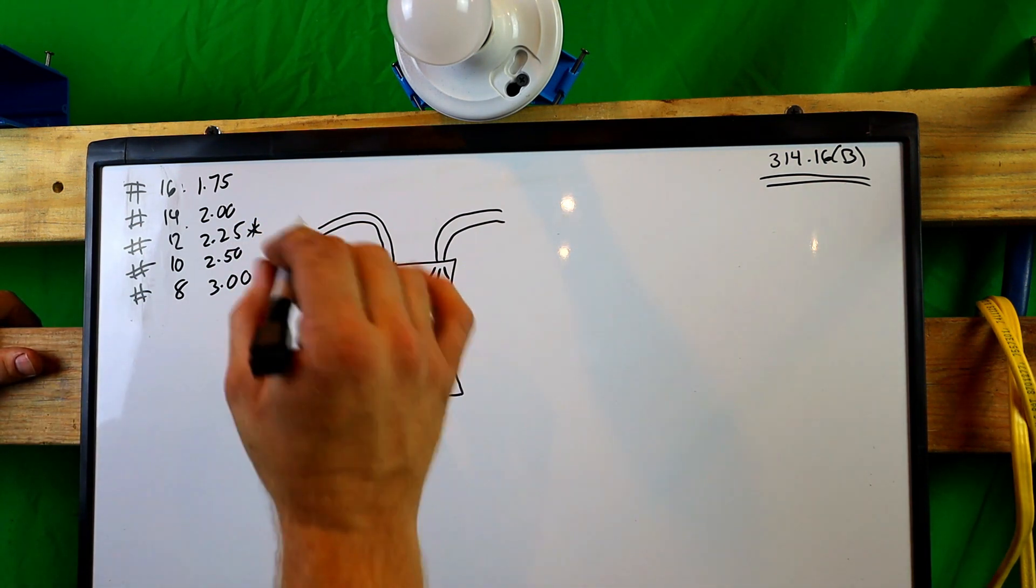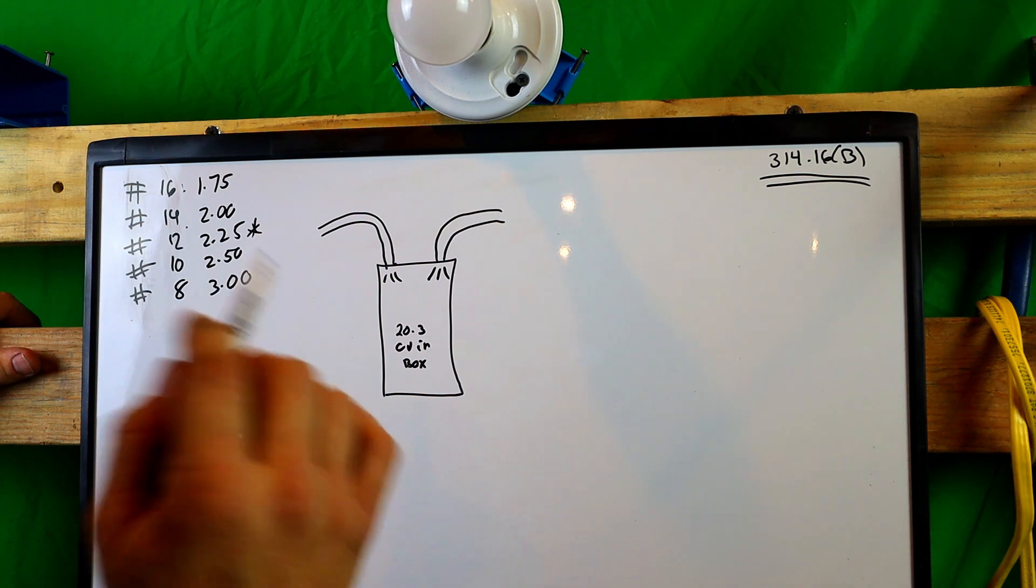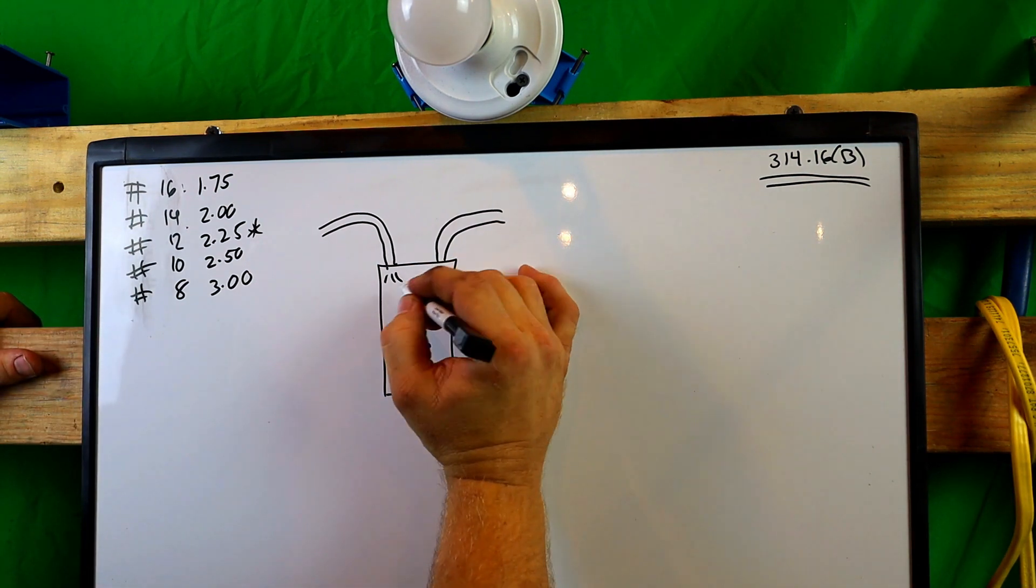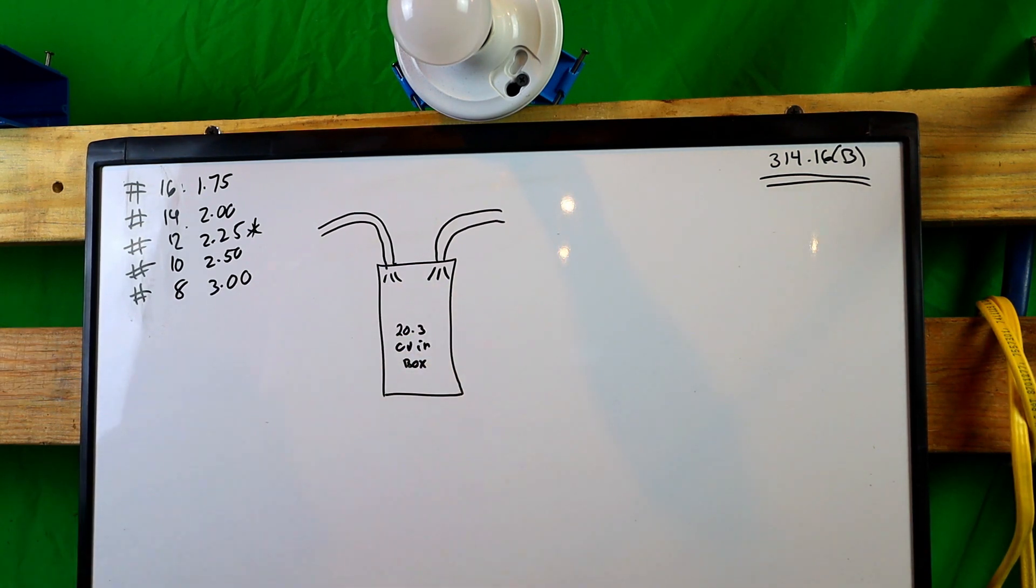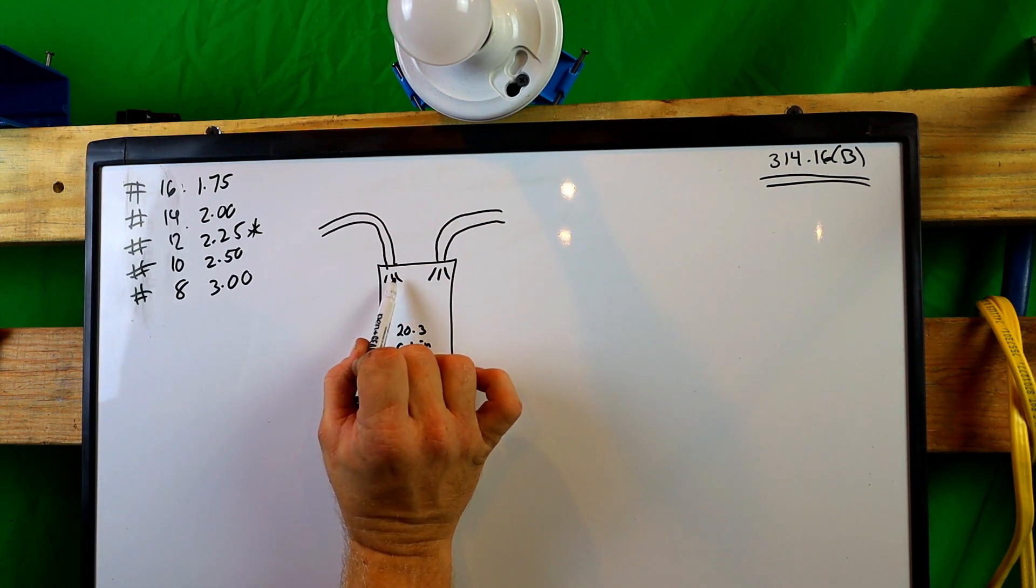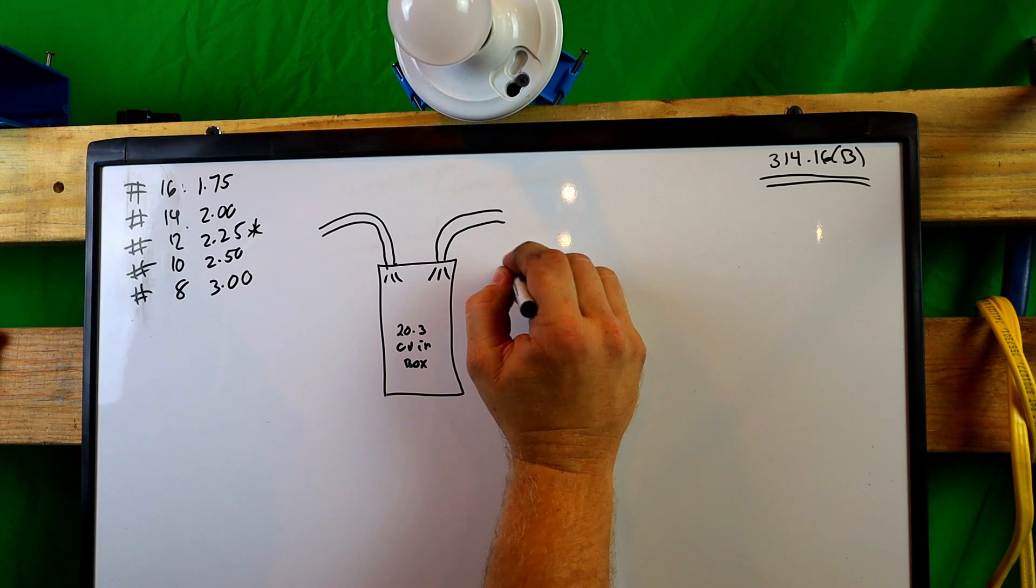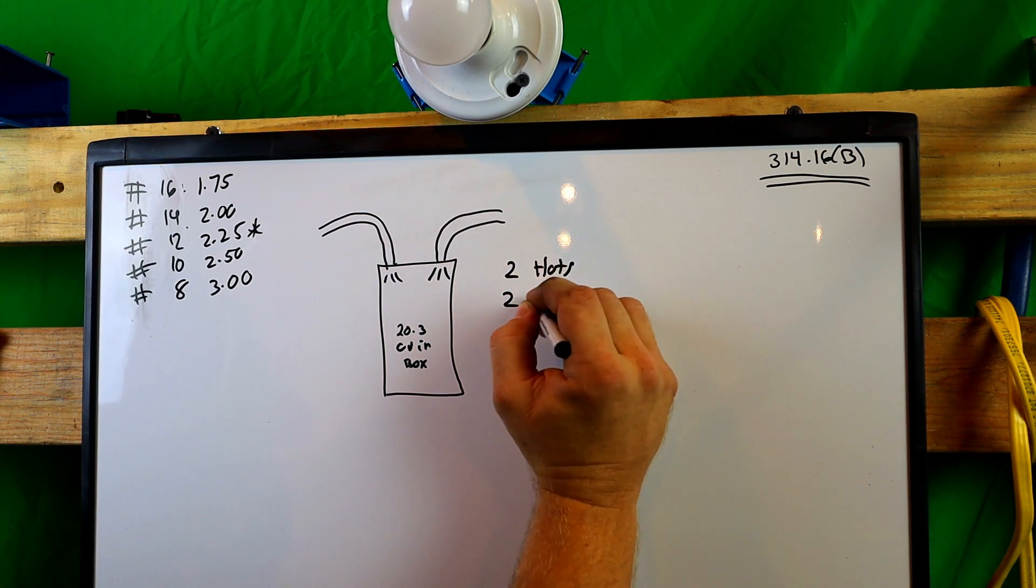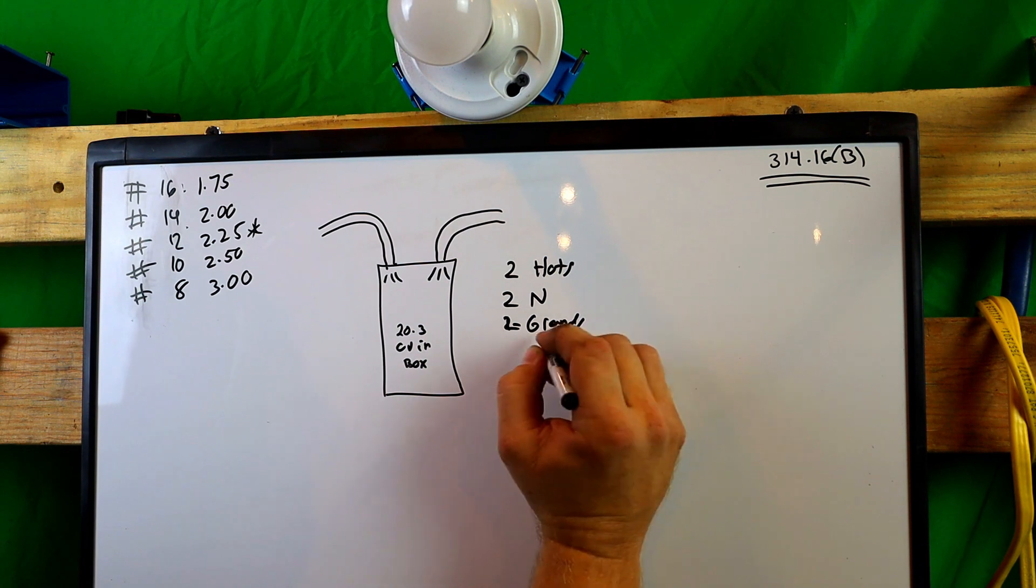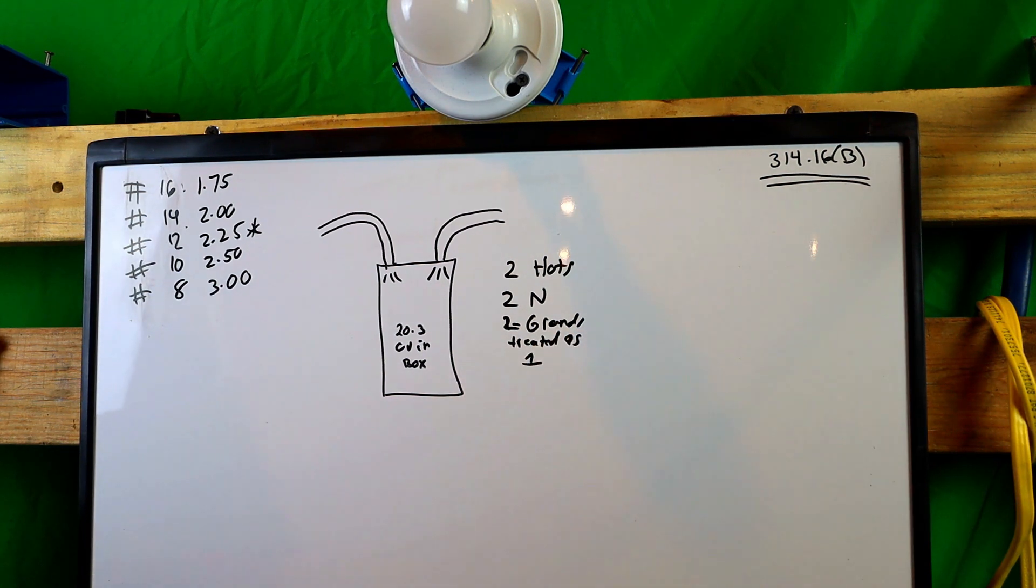So we have three wires in Romex, correct? And we know that the number 12 is rated at 2.25. Now let's stop here and talk about this. There's six wires total, correct? But we are only going to count the ungrounded current carrying conductors, which is your hot and your neutral. The grounds will be counted as a grounding conductor. And these grounds right here, so there's two, will be counted as one wire, even though there's two.